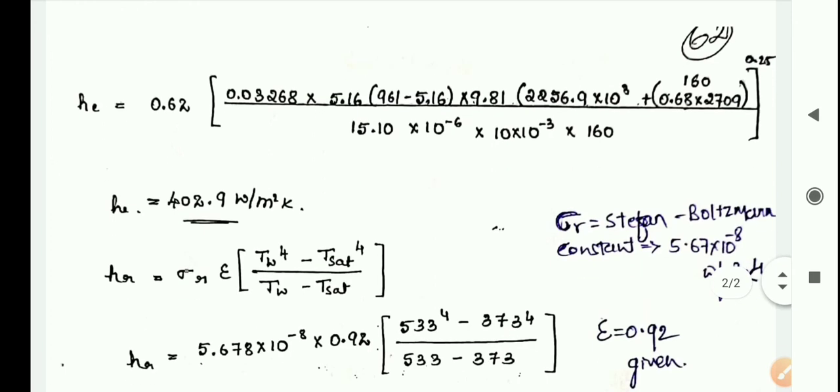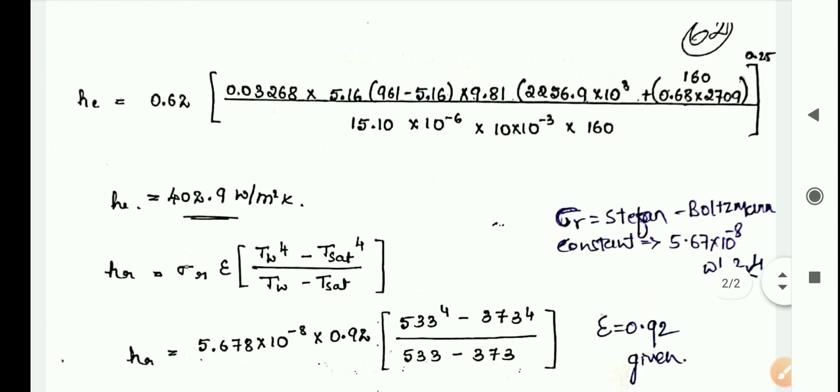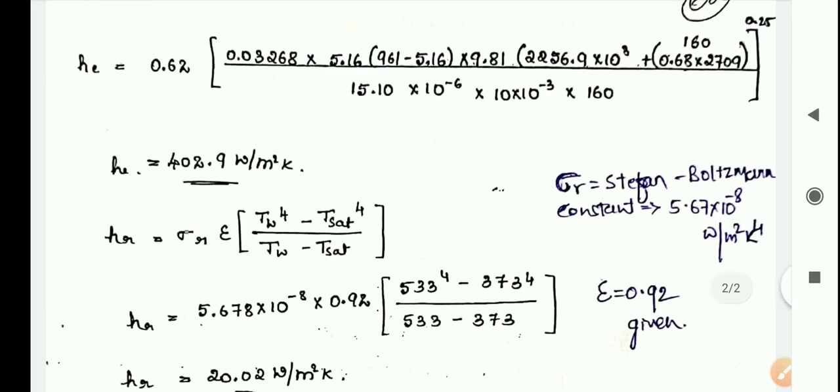Now we have to find hr. For hr, the formula is also available on the same page number 143. That is sigma r times epsilon times (Tw raised to 4 minus Tsat raised to 4) divided by (Tw minus Tsat), where sigma r is the Stefan-Boltzmann constant, 5.67 times 10 raised to minus 8.